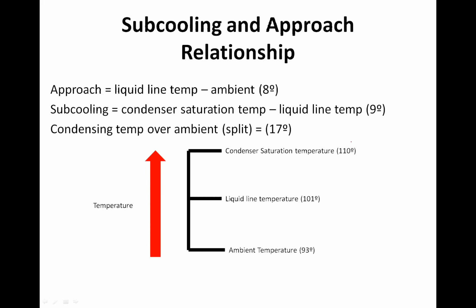There's a couple of relationships you've got to make sure you understand, and you'll hear some different terms out there: approach and subcooling, and then condensing temperature over ambient, CTOA. You hear these things. I want to make sure we cover what they are. If the ambient temperature was 93 degrees, the coldest the liquid line temperature could ever get is 93 degrees, right? The liquid line temperature cannot get any cooler than the ambient air temperature. It's impossible unless there's a problem, like a pressure drop in the condenser.